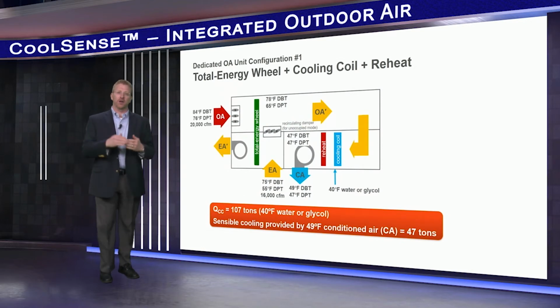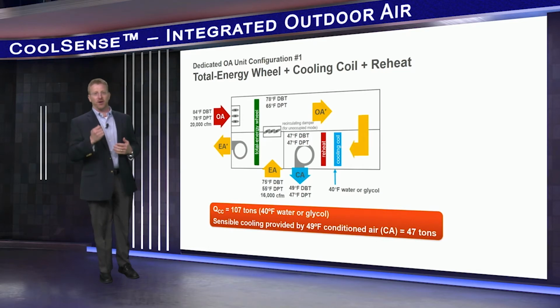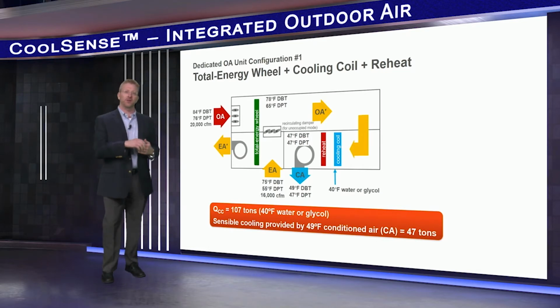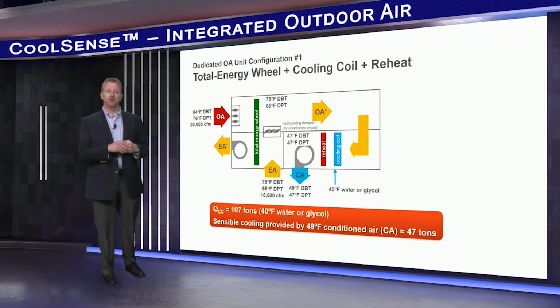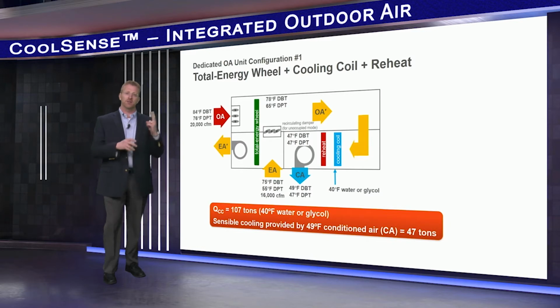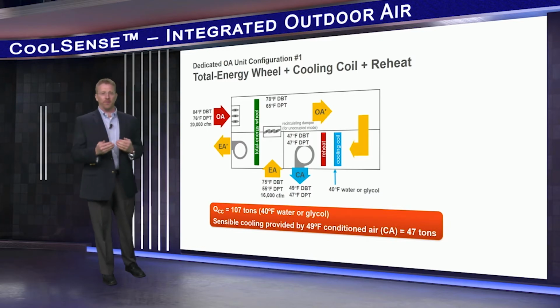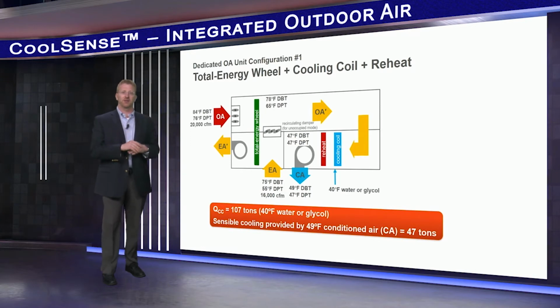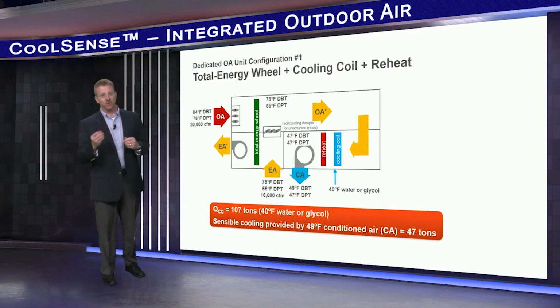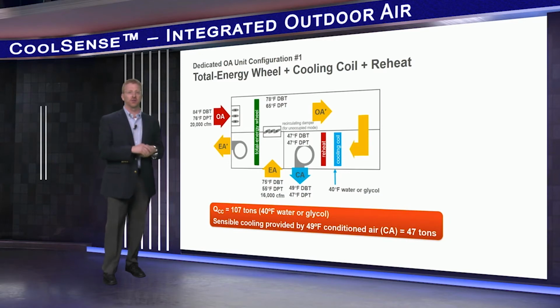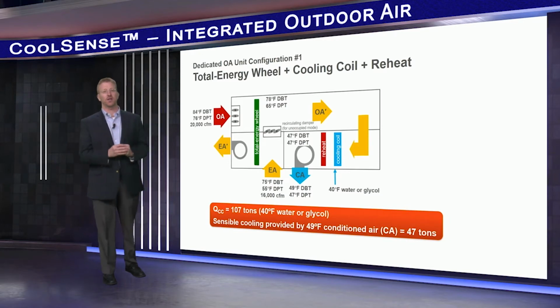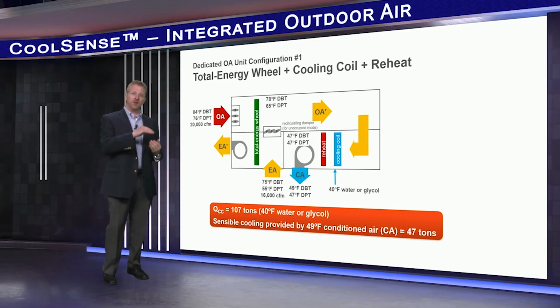I'd like to reinforce a couple of key points just made. First, the unit delivers 49-degree air down the duct at a 47-degree dew point. For this example, we're assuming 40-degree water or glycol is needed to achieve this. Second, the required cooling capacity is 107 tons. If the total energy wheel was not used, it would have been 172 tons, a substantial reduction of 38%. Finally, the cold air delivered to the terminal units offsets 47 tons of the space sensible cooling loads.